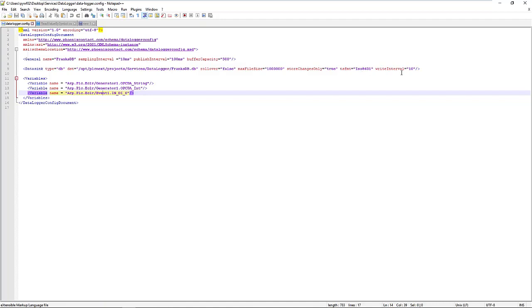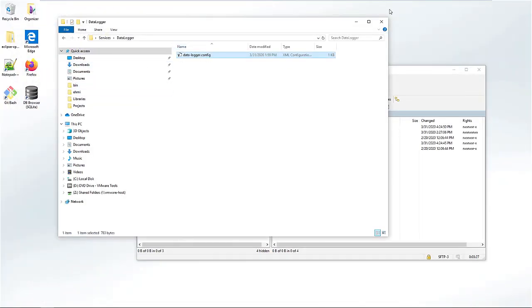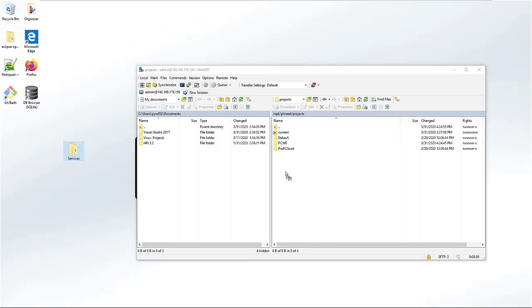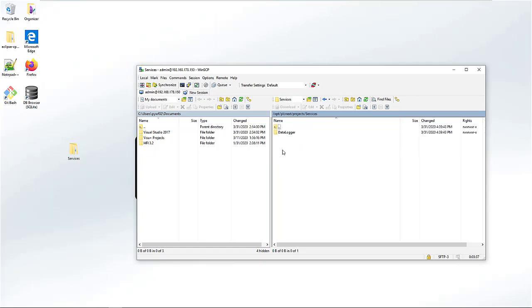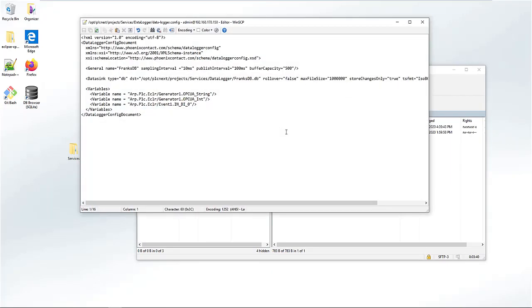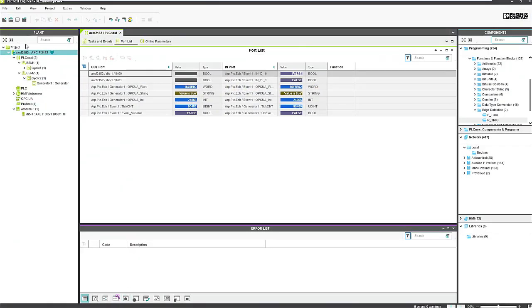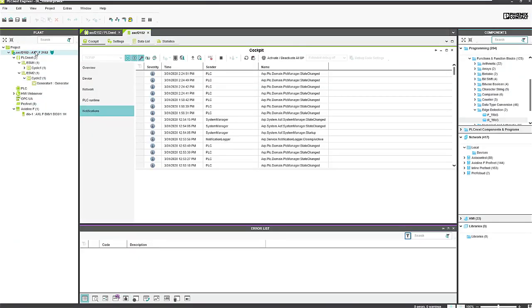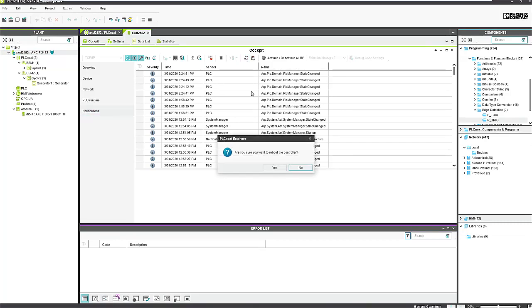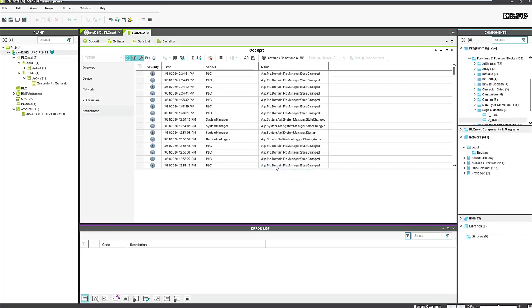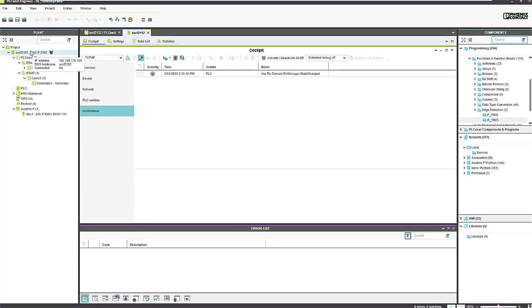And also the write interval to write the values to the SD card. Store all changes and copy the folder to the PLC in the projects directory. Then go back to PLC Next Engineer, open the cockpit, and restart the PLC so that the settings become active. When the PLC is rebooted, we can connect once again.